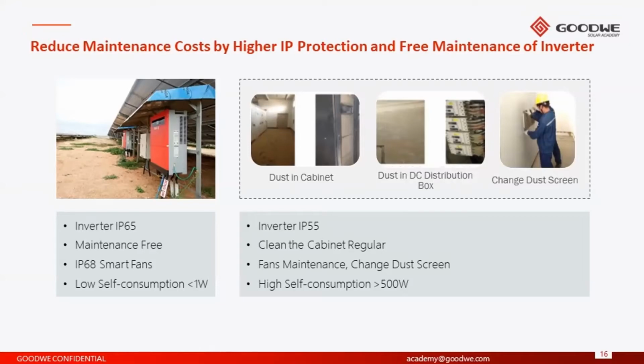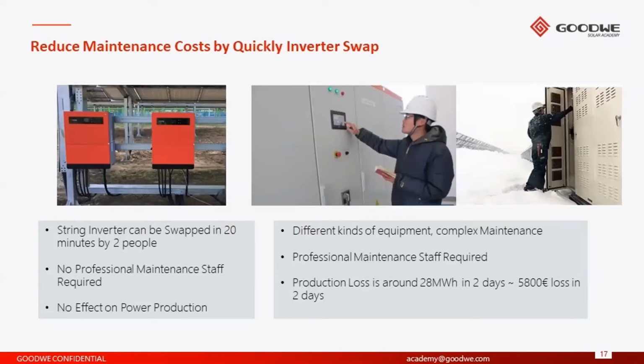Another advantage is in the case of replacements, or needing to add or reduce the number of inverters on site: a string inverter, as you can see, is much easier to replace. It can take up to maybe 20 minutes to be swapped by two people, simply disconnecting the DC outputs and the AC output of the inverter and replacing it with a new one, and the commissioning is quite quick. Typically, you don't need professional maintenance staff or a large crew to replace the inverters. So by having multiple inverters installed on a large commercial installation, replacing one inverter has a small effect on the output of the PV plant.